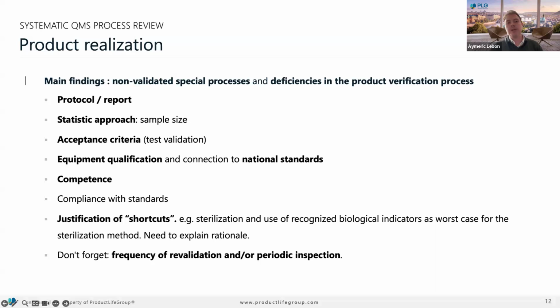The first thing is we really need a protocol really different from the report. In the protocol, we have some different elements from the report. So always have in mind protocol, report. The statistical approach is really important here. It was not so important during the old directive, but right now, yes. And one main element is, can you justify your sample size? If you want to validate your process, if you want to verify your product, how many products did you use? How many repetitions did you do, and why? What is your sample size?